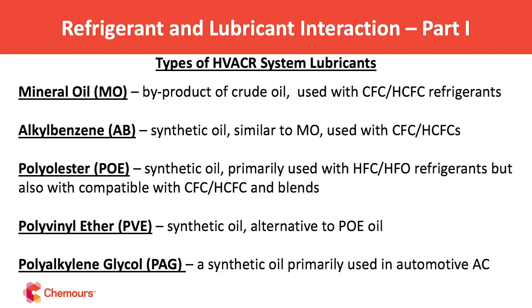For completeness, there are also polyvinyl ethers — very similar to POEs, a slightly more refined grade, a little more expensive, but with some additional beneficial properties. And then polyalkylene glycols, which are predominantly used in the automotive or mobile AC market. We won't cover those today; we'll focus on the stationary side. But let me take a minute to explain what a polyol ester is from a chemistry viewpoint.